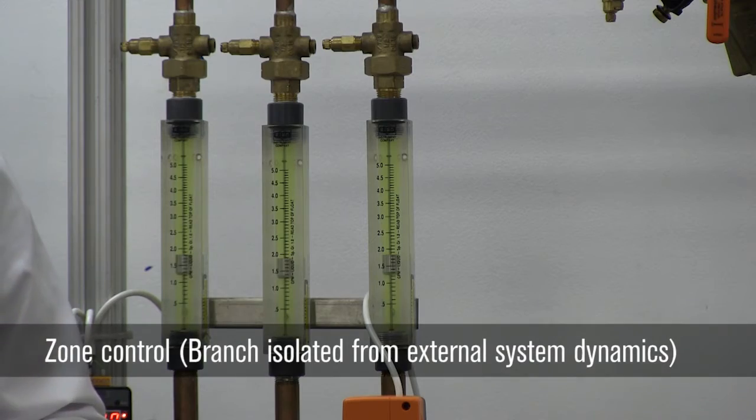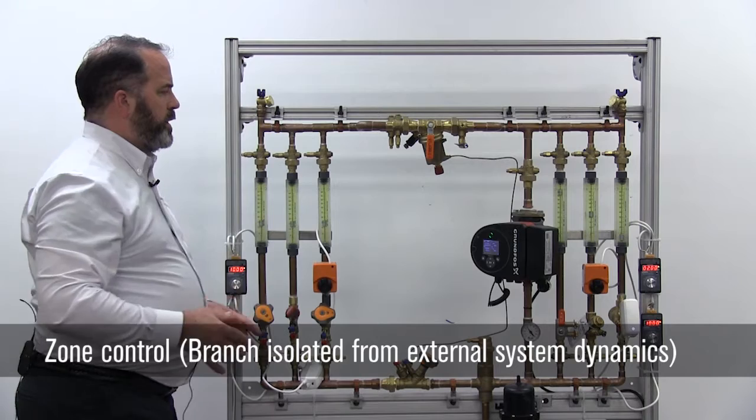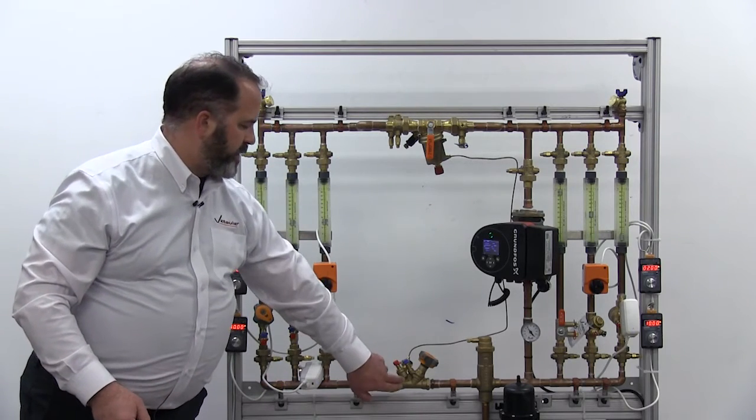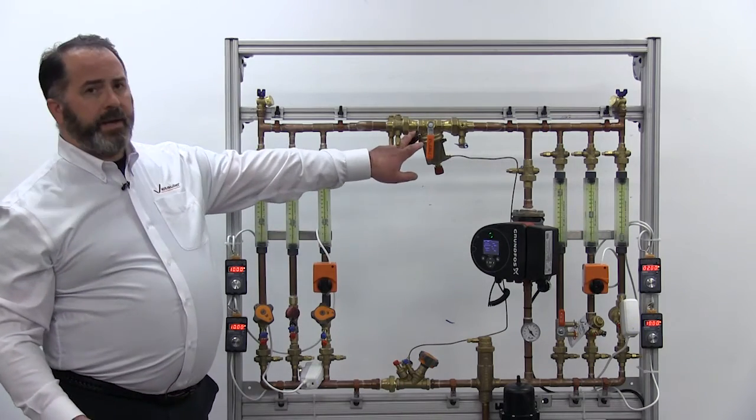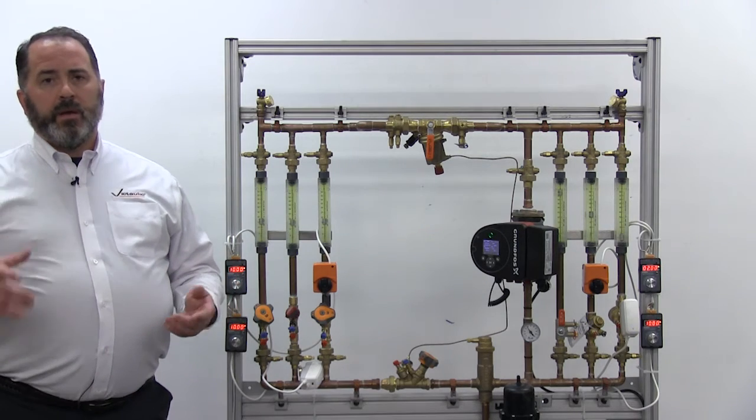So I'm activating the differential pressure controller. Now that valve is controlling the differential pressure between my supply side and my return side, and in doing so I've imparted better control to that part of the system.